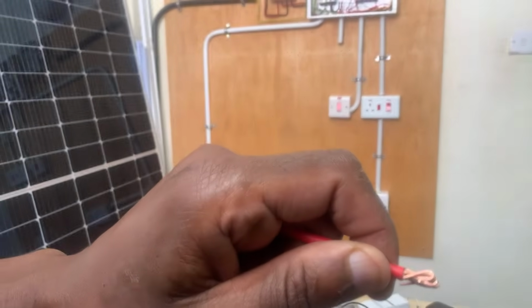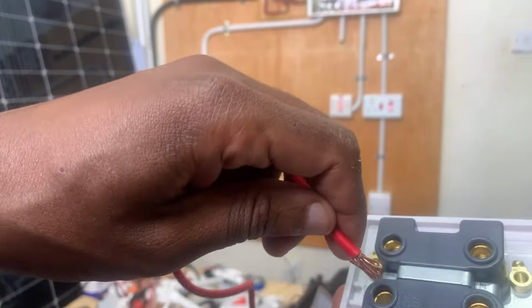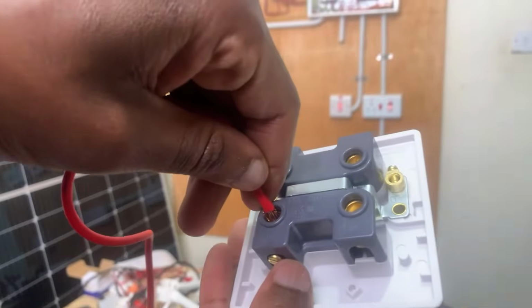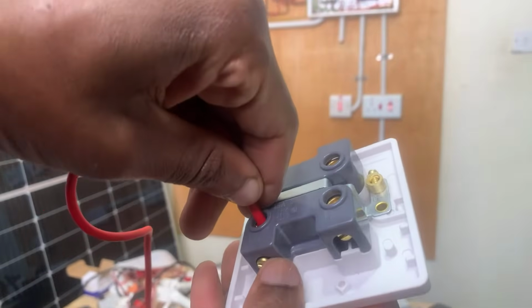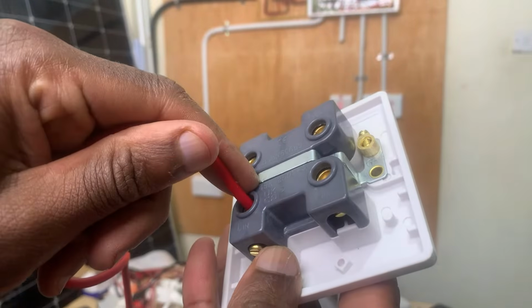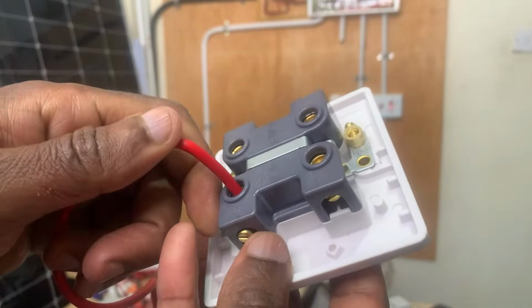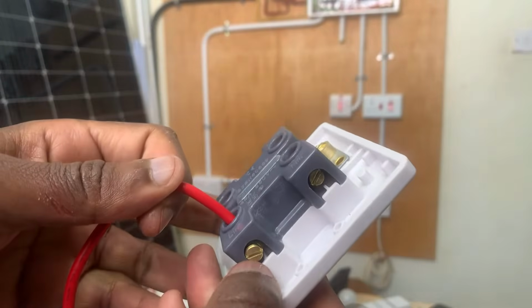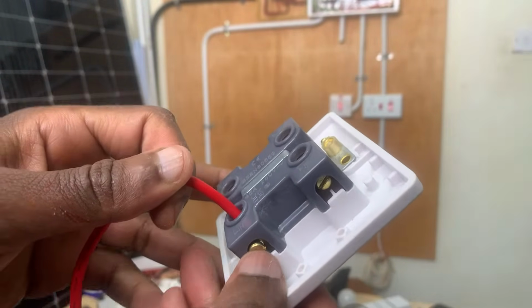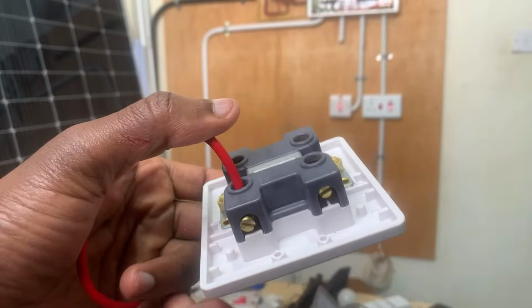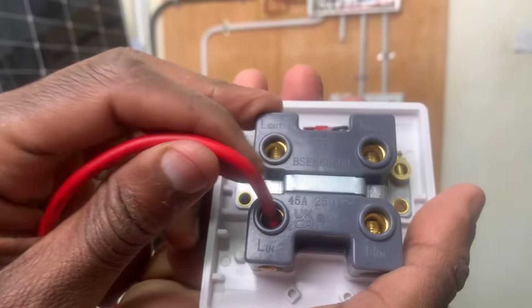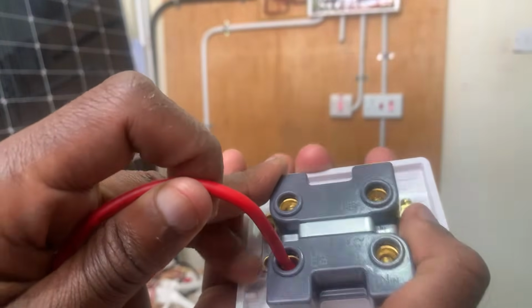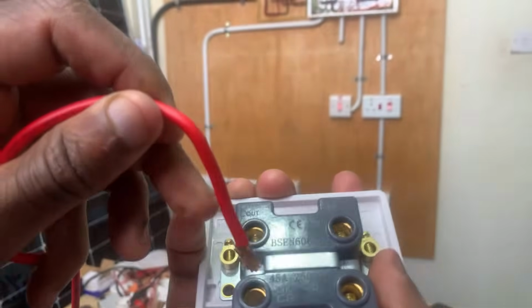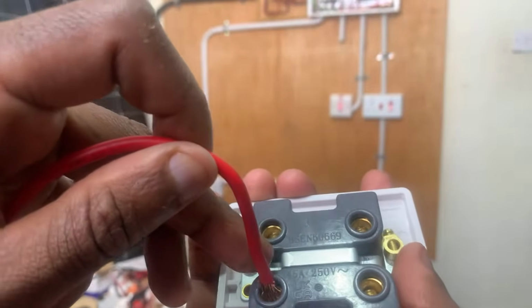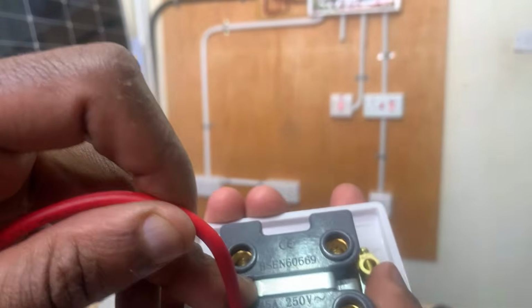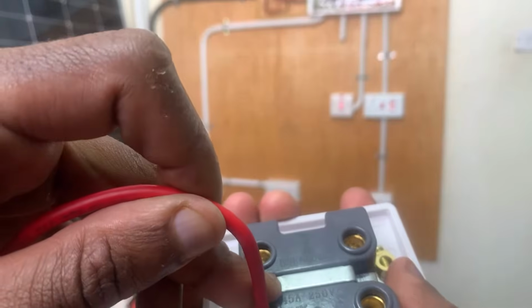Then I will insert it on L. Again, another mistake people make is inserting it all the way in, such that when you screw, you find someone has screwed onto the insulation. That is very wrong. You must check the screw and make sure that before you start screwing, it is only in contact with the cables or wires that you have stripped.